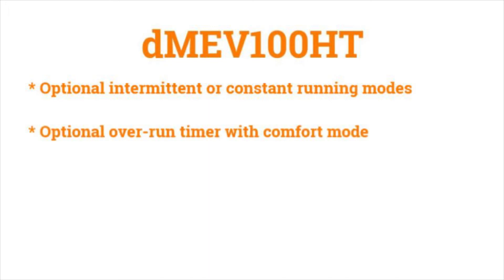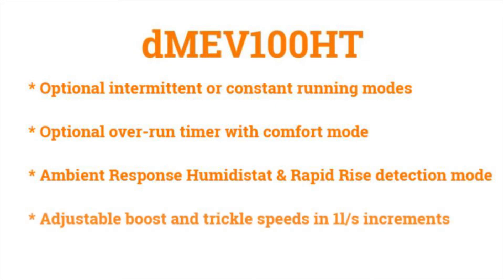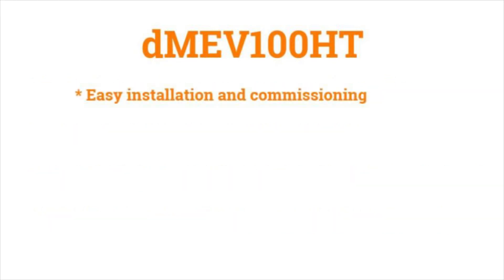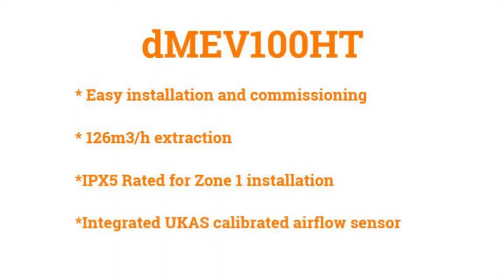These include optional intermittent or constant running modes, optional overrun timer mode with comfort mode to prevent nuisance activations for short bathroom visits, two different optional humidity functions with ambient response humidistat and rapid rise detection, adjustable boost and trickle speeds in one-litre-per-second increments, easy installation and commissioning with a simple LED programming interface, an impressive 126 metres cubed per hour of extraction on its highest boost setting, and IPX5 rating for zone 1 installations, along with an integrated UKAS calibrated airflow sensor.